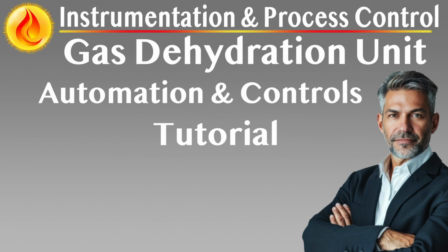Glycol pump protection and transfer monitoring. Pump discharge pressure and flow. Pressure transmitters on the lean glycol pump outlet verify integrity and check valve function. Flow measurement confirms proper circulation rates. Pump seal leakage detection. Leakage sensors or drip pans with proximity switches identify seal failures for maintenance intervention. Pump interlocks. Low suction pressure or high discharge pressure automatically isolates the pump. Vibration sensors, if rotary or centrifugal, monitor for mechanical degradation.